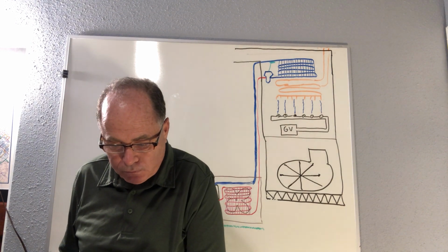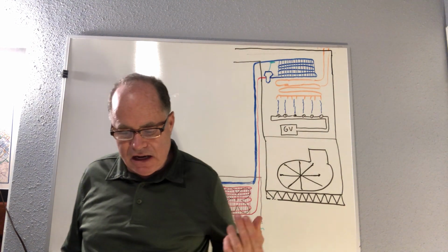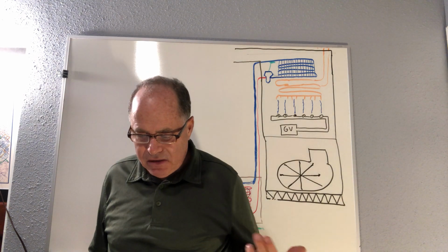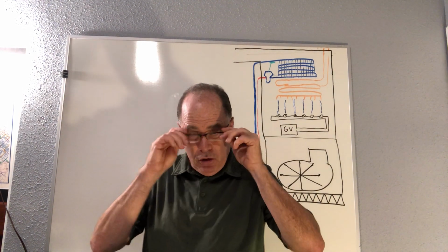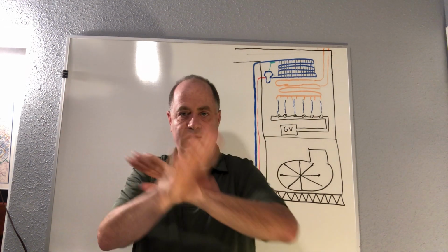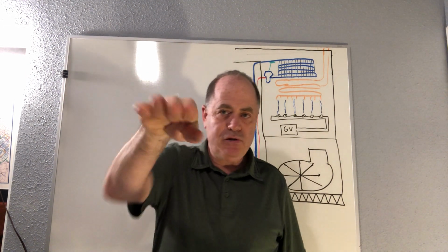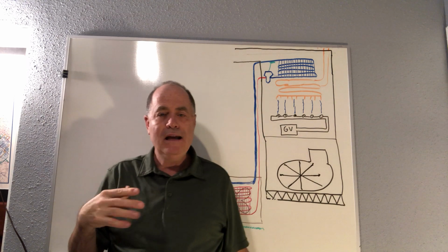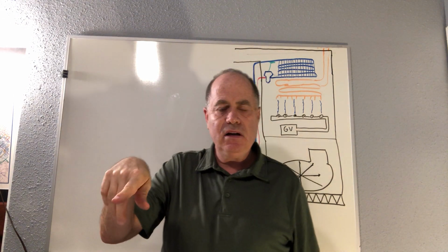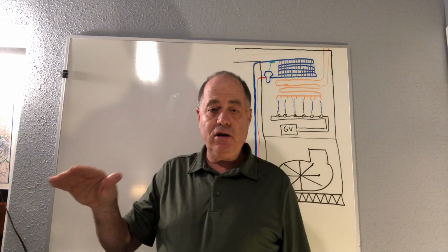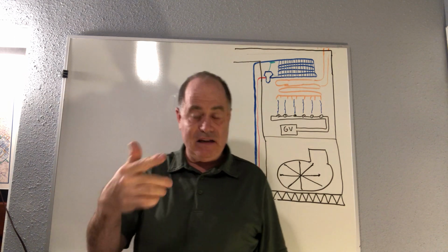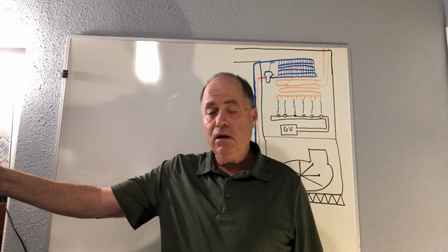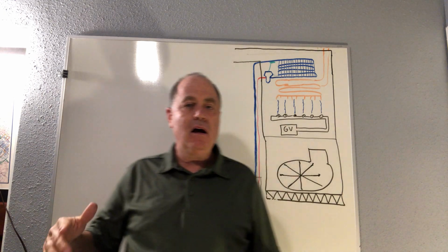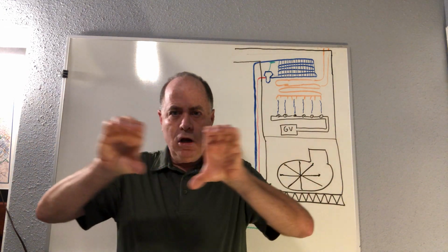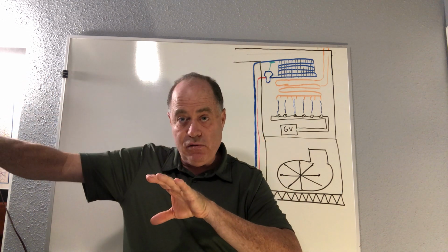And then a unit heater shall not be attached to a warm air duct system unless marked for such installation, right? Most of these unit heaters have prop fans, just like a box fan type that blows the air through. And I have kind of a general rule that says we use prop fans when there is no change in direction of airflow and no duct work. Condenser fans, just through the condenser and out, are any kind of prop fan. Think of a window unit with one motor and 2 fan blades on the end. The one for the condenser is a prop fan right through the condenser and out.